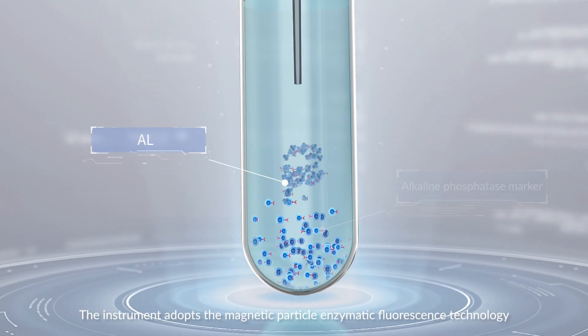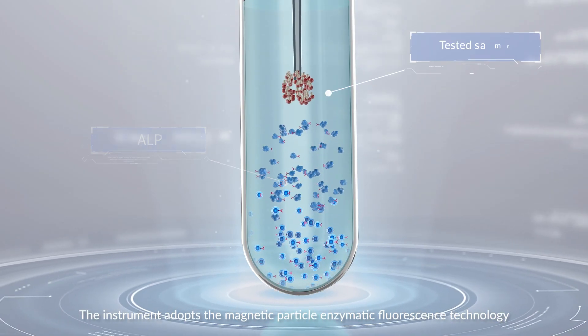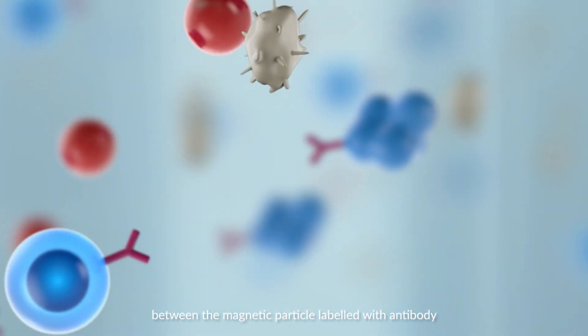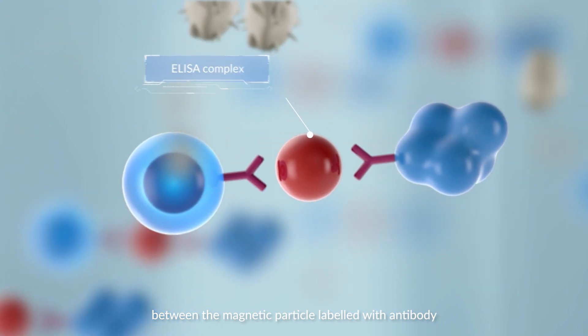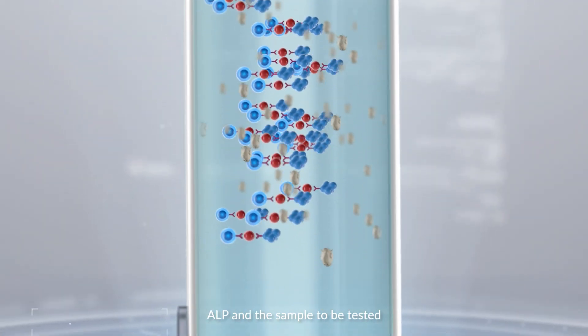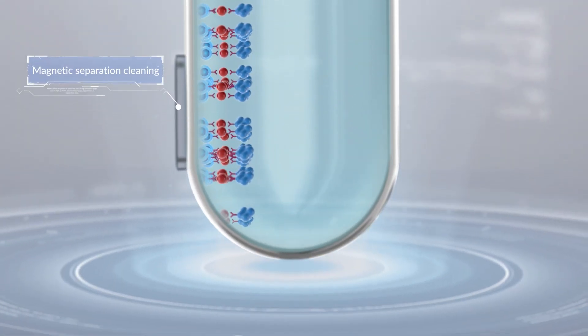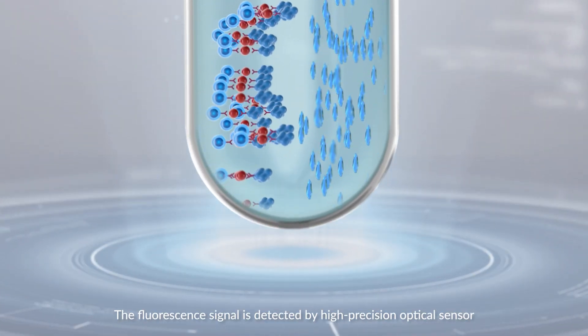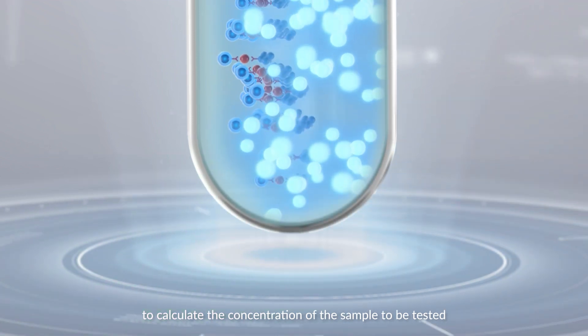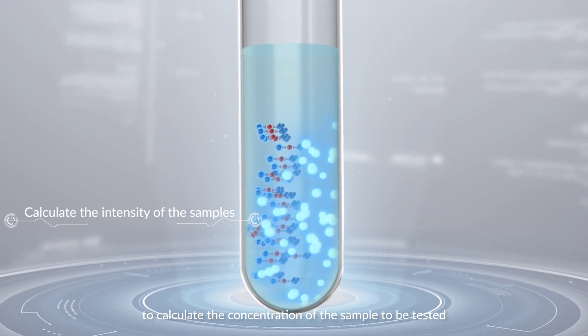The instrument adopts the Magnetic Particle Enzymatic Fluorescence Technology to generate immune reaction between the magnetic particle labeled with antibody, ALP, and the sample to be tested. The fluorescence signal is detected by High Precision Optical Sensor to calculate the concentration of the sample to be tested.